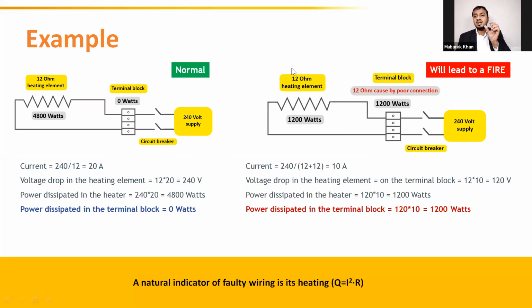Under this scenario, if you apply Ohm's law, there will be 10 amperes of current flowing through the circuit, which will cause a 120 volt drop across the heating element, as well as a 120 volt drop across the terminal block, which will cause 1200 watts of energy to be dissipated on the heater as well as the terminal block. The heater is designed to withstand a large amount of energy, so nothing will happen to the heater, but the terminal block will not be able to withstand that much energy, so that energy will convert into heat and it will burn the terminal block. So what we understand from this is that the natural indicator of faulty wiring is its heat. If connections are not tight, the joints will get heated. So what we do is monitor the heat to identify the loose connections.